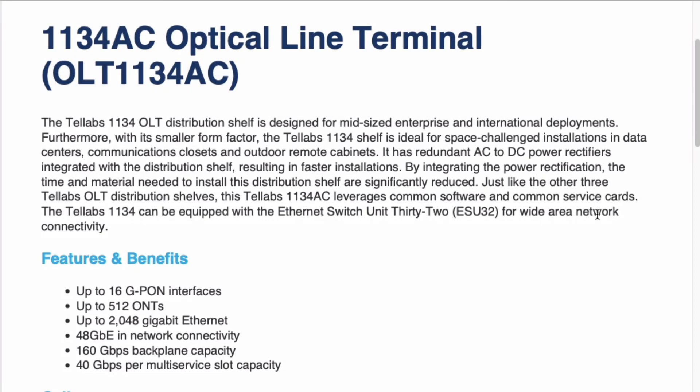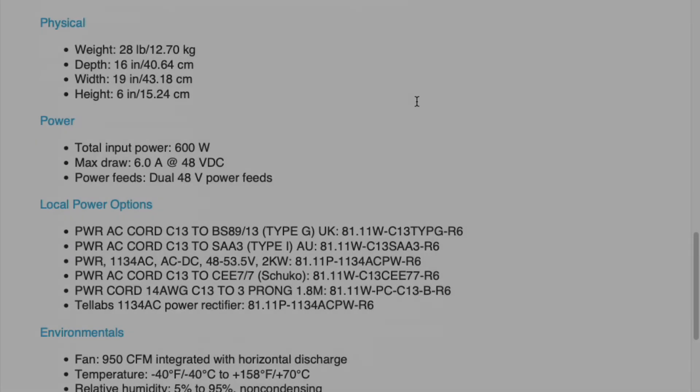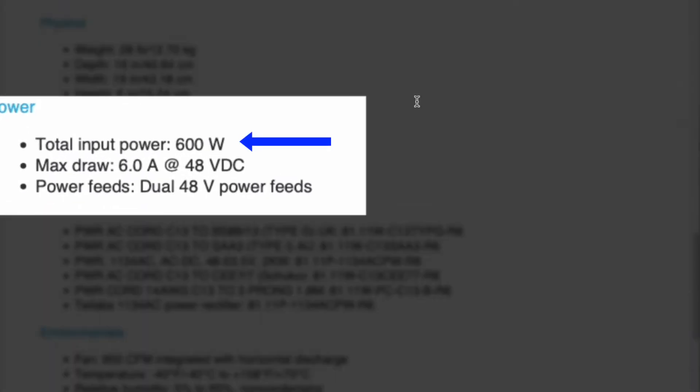The customer has told us they'll be using a Tellabs 1134AC optical line terminal which can supply up to 512 ONTs. Referring to the input power specs for this device we see that we need to provide 600 watts of 48 volt power.